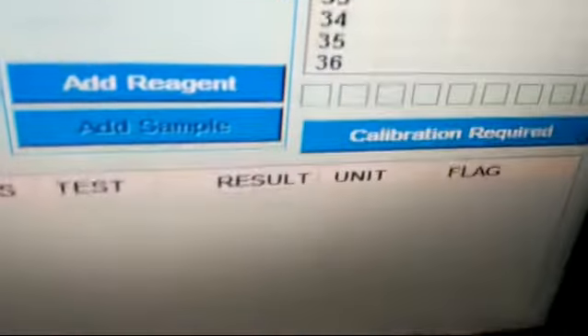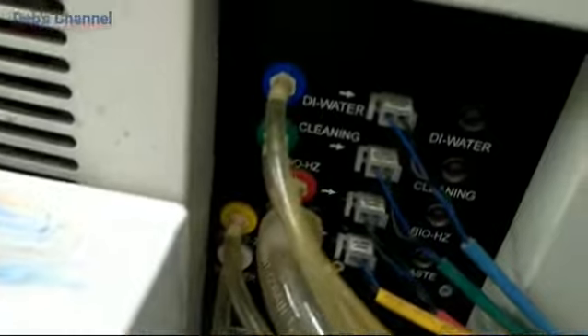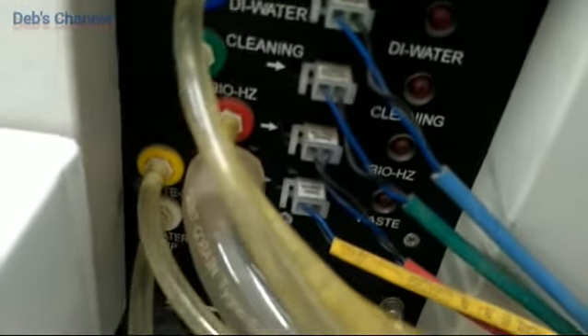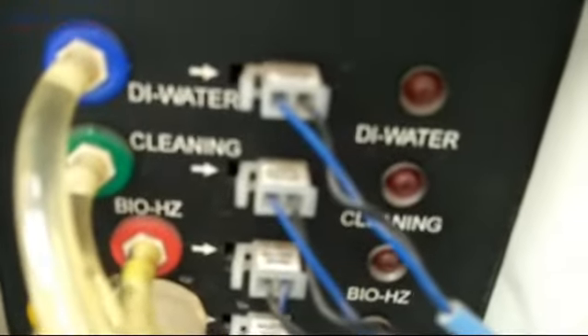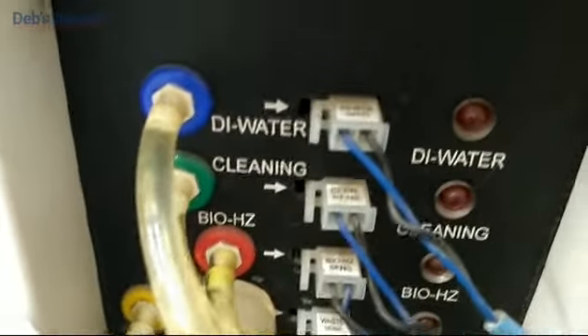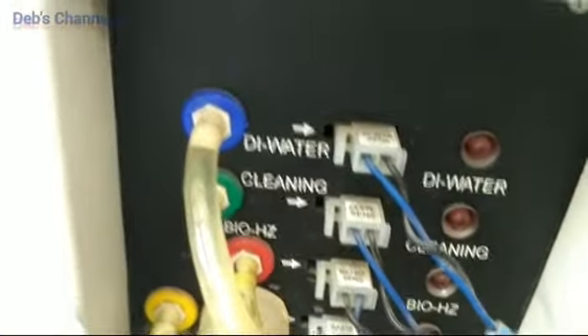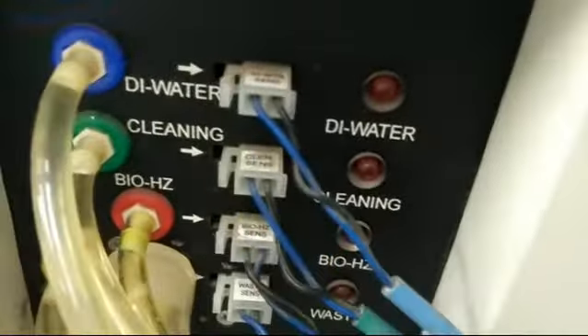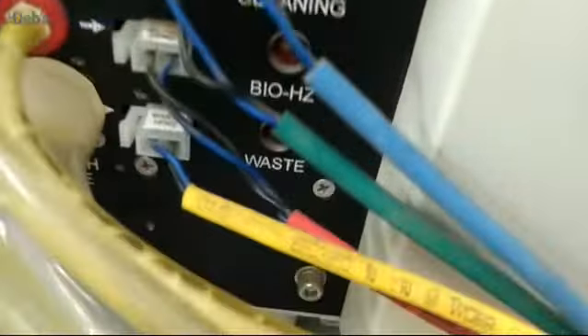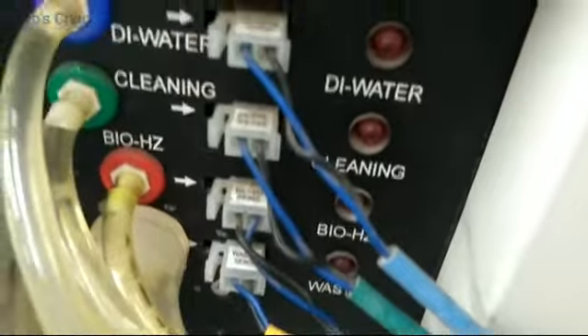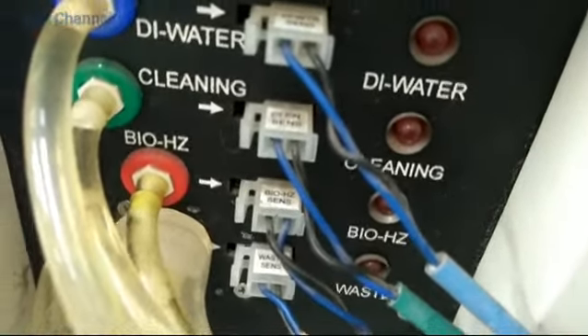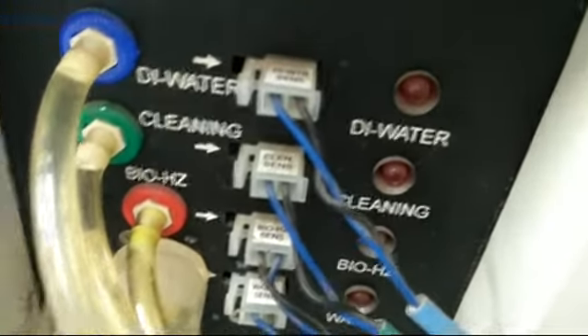But if we make any mistake in programming, then there is a function for rectification of the program. This is the back portion of the machine. There are some LED indicators, you can see them, like the DI water, the cleaning, and the biohazard. DI water is required, and whenever the level of the DI water decreases below the specific level, then a siren will be on. In case the biohazard bottle overflows, then the siren will also be on and the test will stop automatically. After cleaning up and filling the DI water, the test will run automatically.